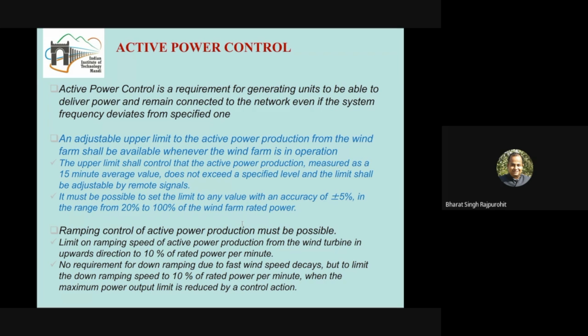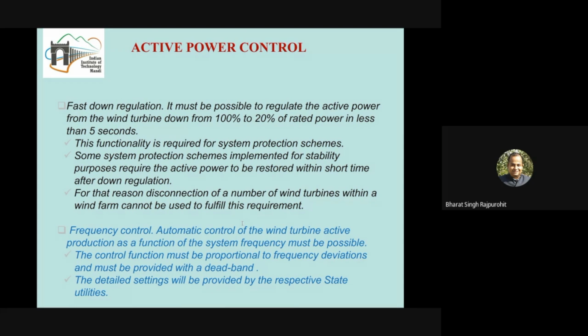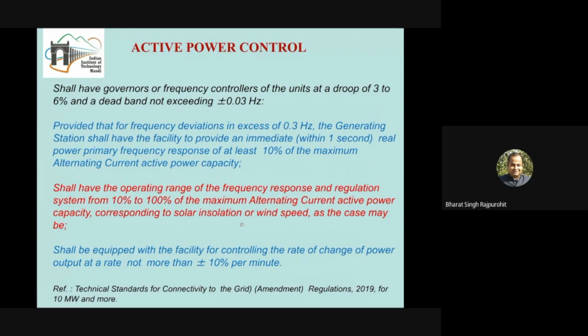Fine. Now please see all this data that I was talking about. Let's see, the adjustable upper limit is there. It means 20 to 100% power can be changed. Ramping control says that in the upward direction it is 10% of the rated power per minute, and similarly for the downward direction also. These rates are prescribed by the Indian electricity grid codes. Then fast down regulation says that 100% to 20% of the rated power should be reached within 5 seconds. Then frequency control I have already mentioned.